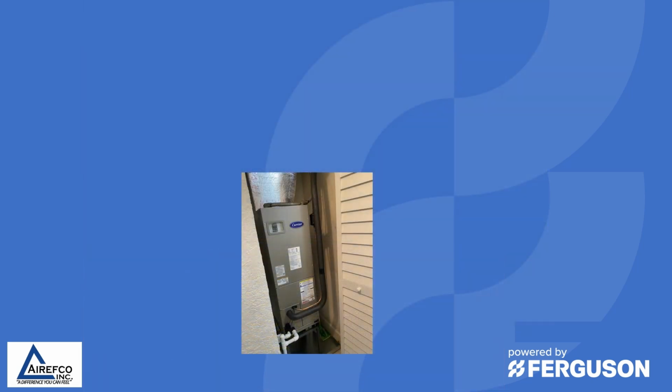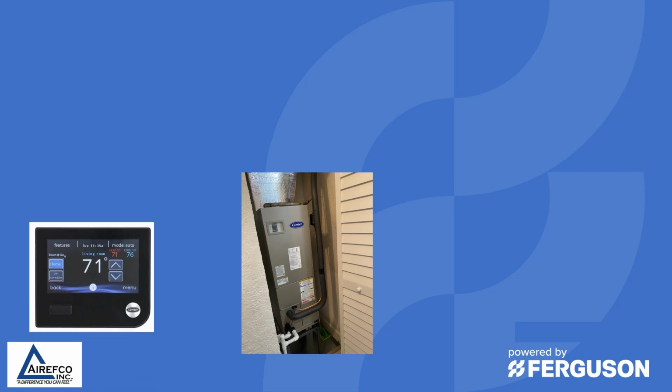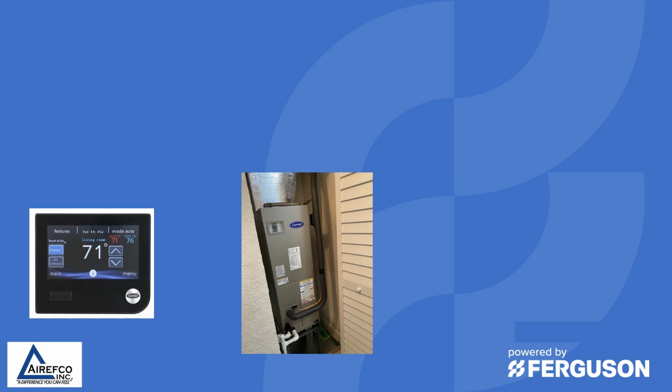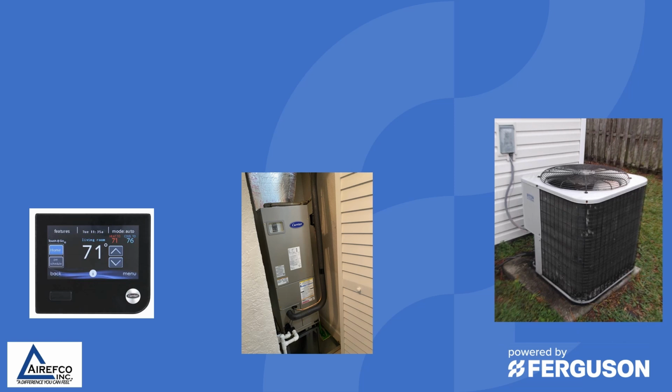So I'm going to use a recent case to try to point out to you how to isolate components in a system to try to find the problem. When you have a Carrier or a Bryant communicating system, you have to start with a communicating indoor unit, either a gas furnace or a fan coil. Then you'll have the user interface that communicates with the fan coil or furnace. Then you may have an outdoor unit that is communicating with the system.